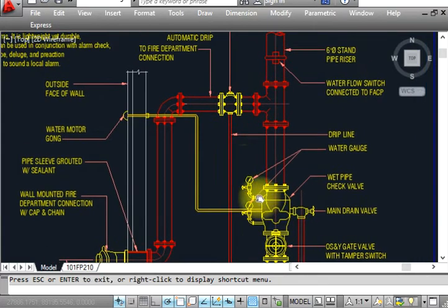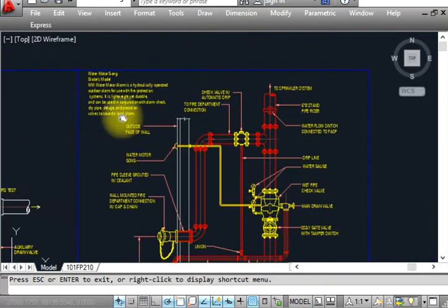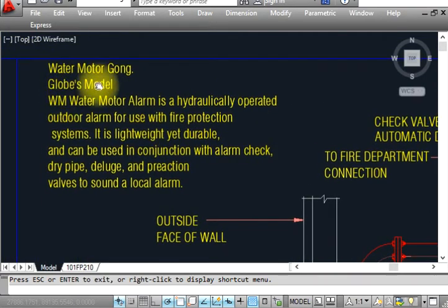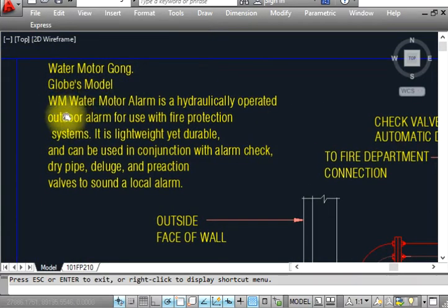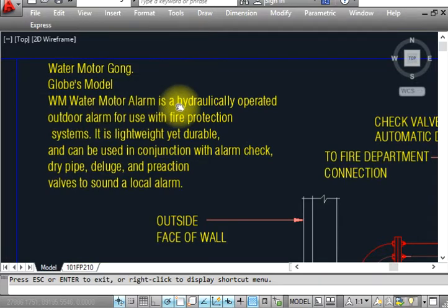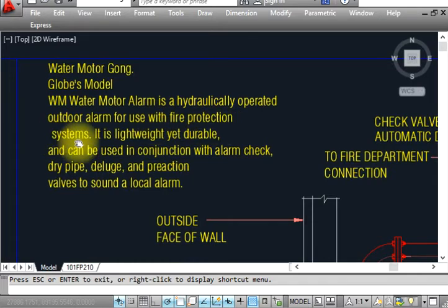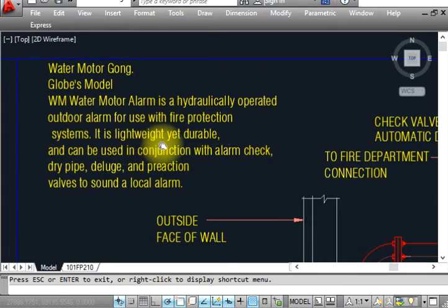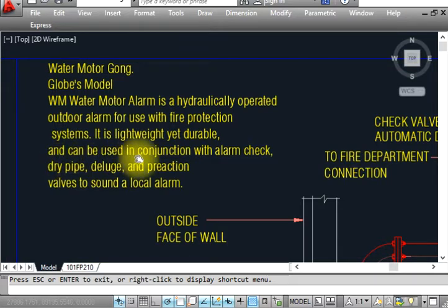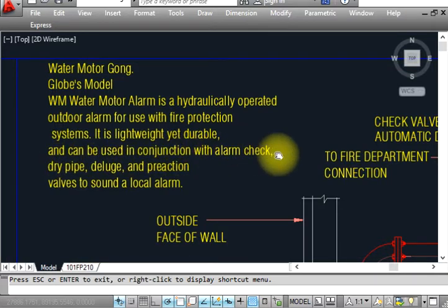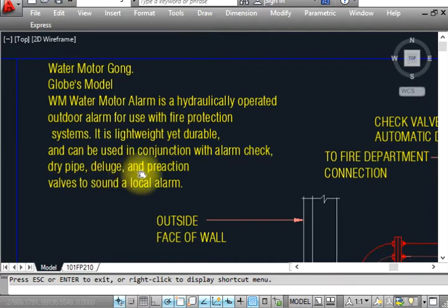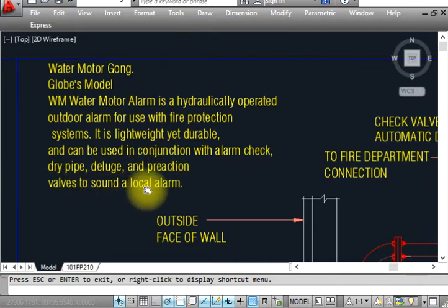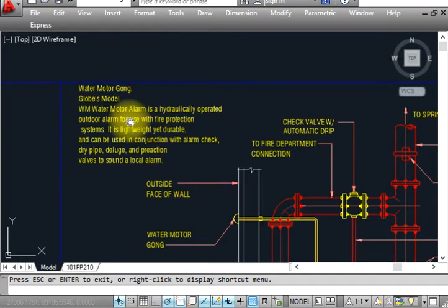What is the definition for water motor gong? I already wrote here: Water motor gong, water alarm, is a hydraulically-operated automatic alarm for use with fire protection systems. It is a highly durable unit and can be used in conjunction with alarm checks, dry pipes, deluge, and preaction valves to sound a local alarm.